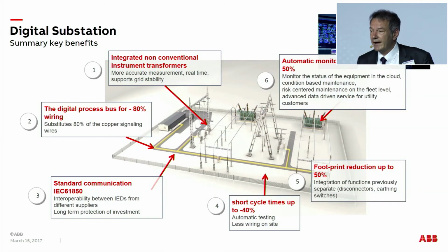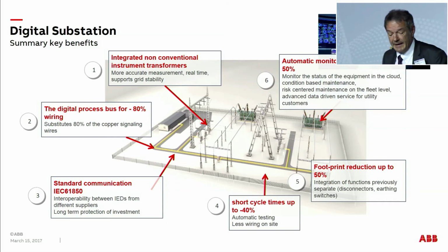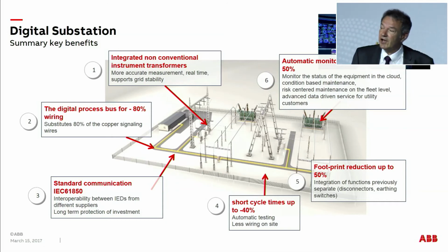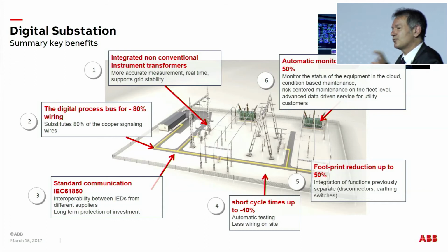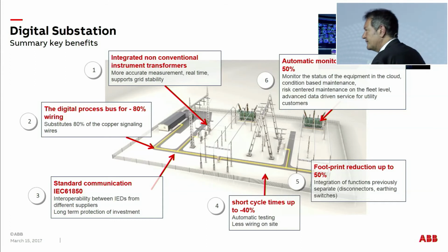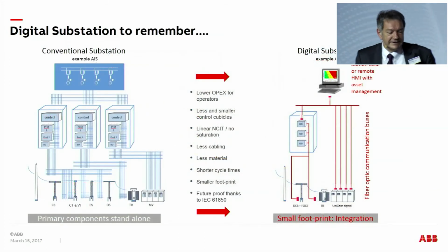We can reduce the wiring by 80%. We have a standard communication, the standard is IEC 61850-9-2, an IEC standard. Then we have a footprint reduction of up to 50%, as I was explaining. So the size will shrink. And we will have operational expenditure reduction of up to 50%, because you can much more efficiently service and monitor your equipment. So this is digital substation.